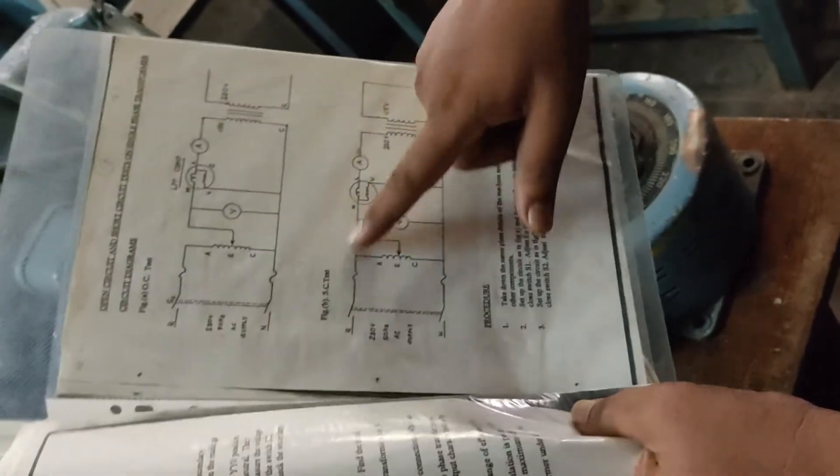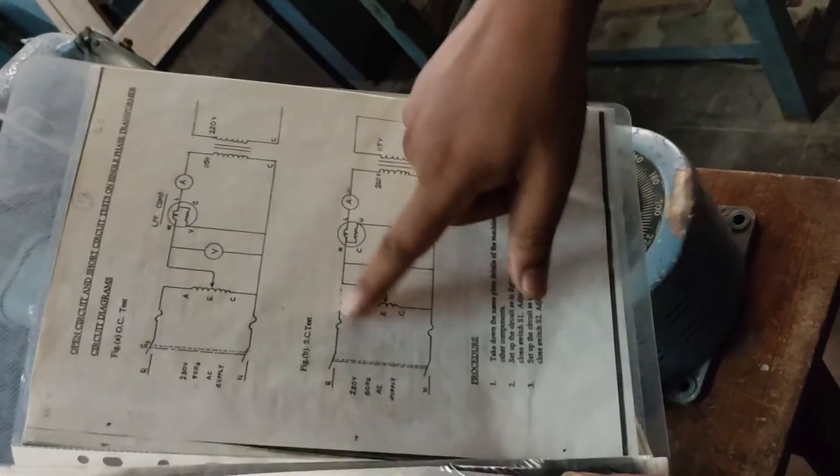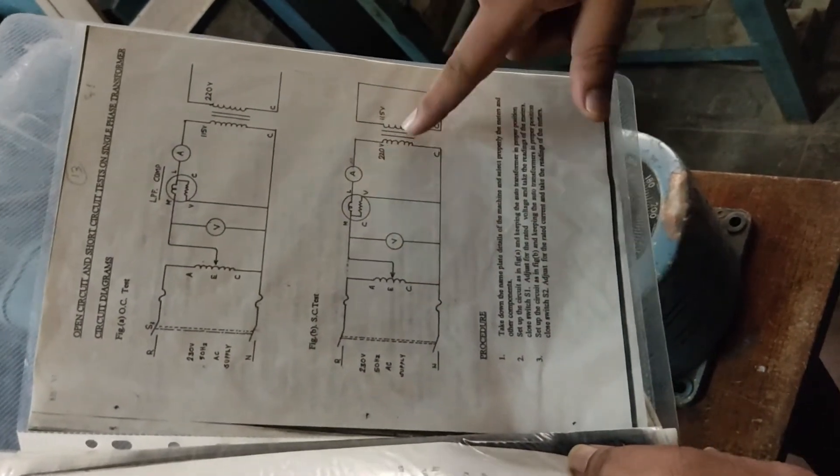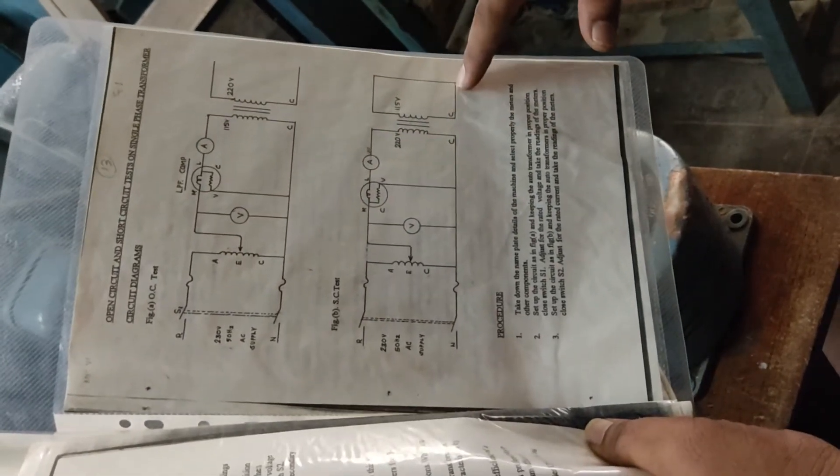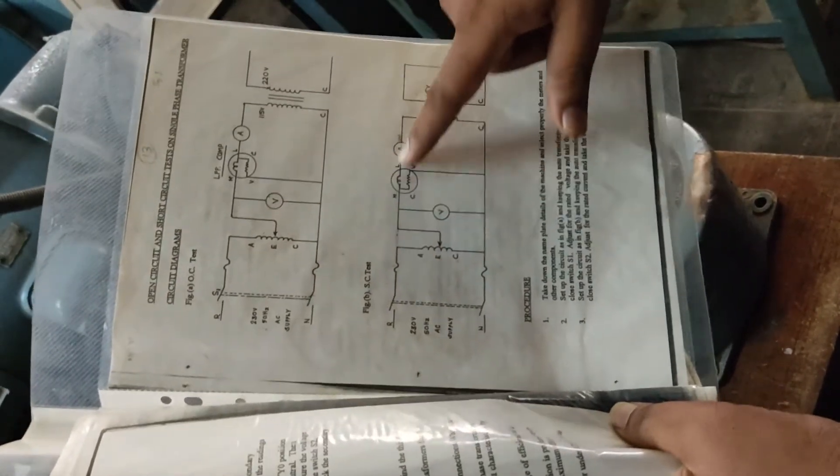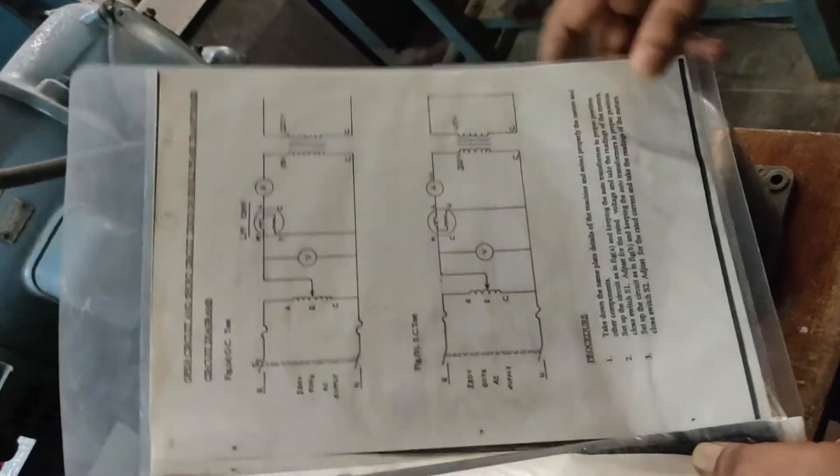This is a short circuit test on a single phase transformer. Supply can be given through a variac to the transformer. The supply is given to the high voltage side and the low voltage side is shorted. Required instruments include a voltmeter for input voltage, an ammeter in series with the phase, and a wattmeter to measure the power input. The output side is short circuited.